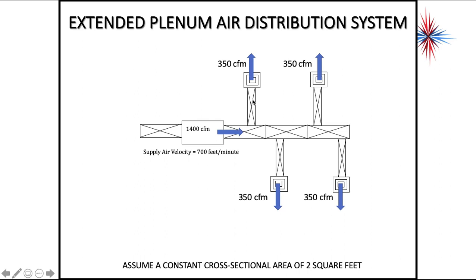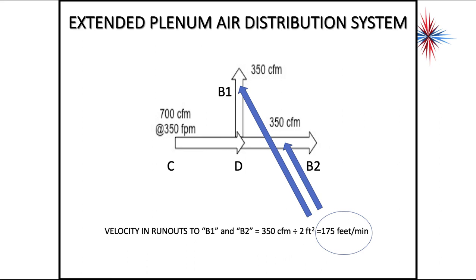Depending on the system, you may hear airflow out of here, but you may not hear airflow out of here. So the only way to be sure is to measure it. Hopefully that makes a little sense. But your velocity drops as you go forward. That's the extended plenum system. One size duct work fits all. It's very, very frequent, especially if you're dealing with duct board and not sheet metal.